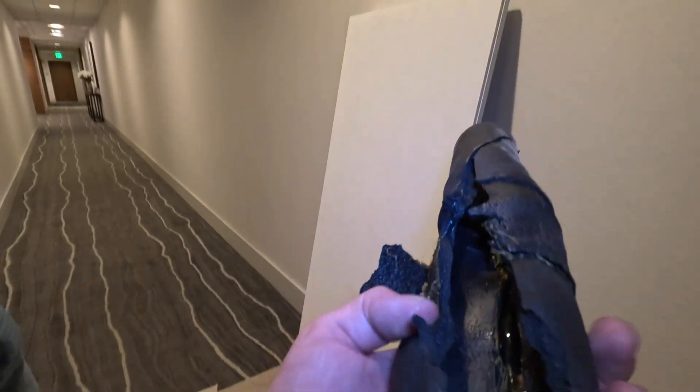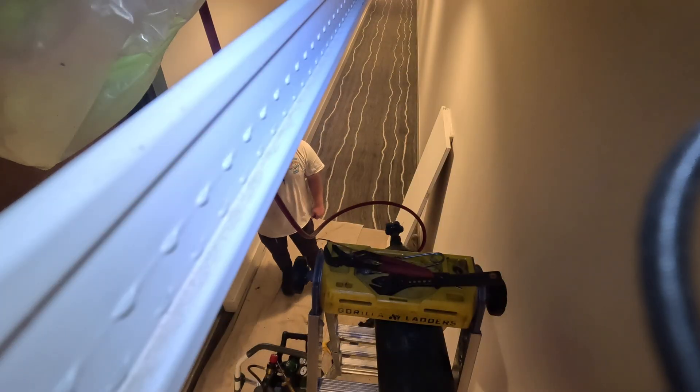You can see all that oil — there's evidence the leak was there. We bubbled it up and found it. It seems to be holding higher now. I think it might just be the system pressure equalizing, to be honest. It might just do it kind of funny. I'm just emptying this whole tank into there, and I'm going to close this. I think that's a pass on the pressure test, in my opinion. If we want to start vacuuming, we can do that.